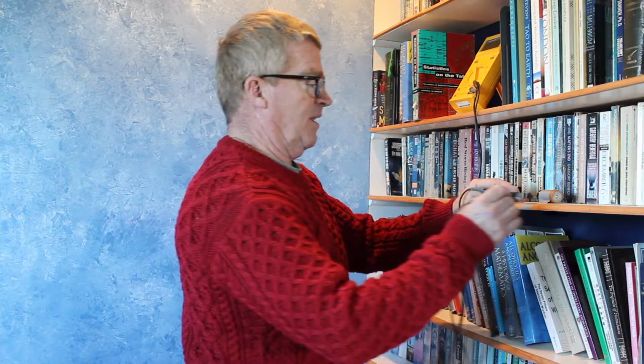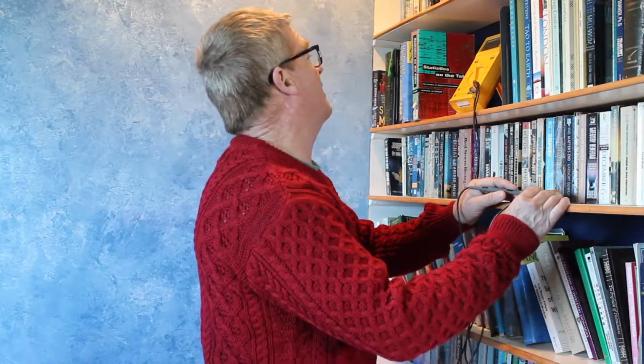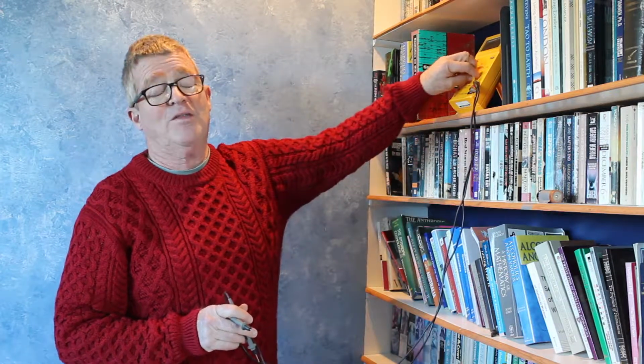So let's try and do a measurement. I'm going to measure the DC value of this DC source that happens to be duct taped to the bookcase. Okay, here we go. There we go, I got a measurement. And like a good tech, I'm going to turn the thing off to save the batteries. Now, what is it about what I just did that's traceable? I already told you that the standards back in the lab that certified this thing are not in themselves traceable. This meter is not traceable, but in some cases, the readings that I just took could be traceable. So what's this all about?